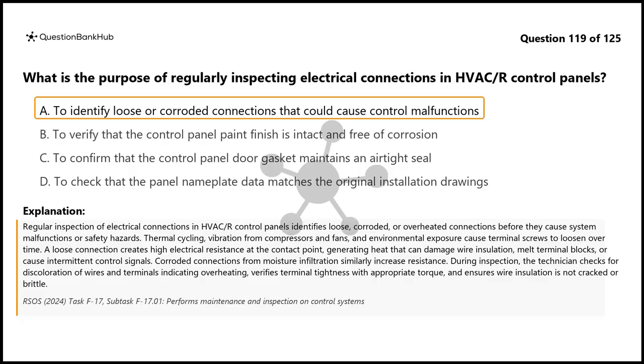A loose connection creates high electrical resistance at the contact point, generating heat that can damage wire insulation, melt terminal blocks, or cause intermittent control signals. Corroded connections from moisture infiltration similarly increase resistance. During inspection, the technician checks for discoloration of wires and terminals indicating overheating, verifies terminal tightness with appropriate torque, and ensures wire insulation is not cracked or brittle.